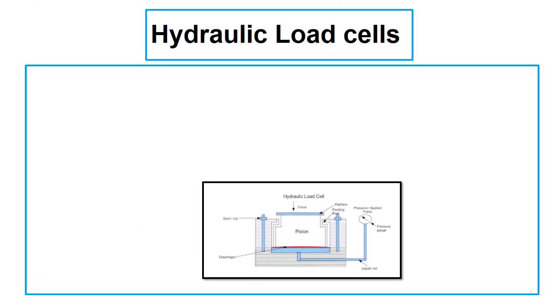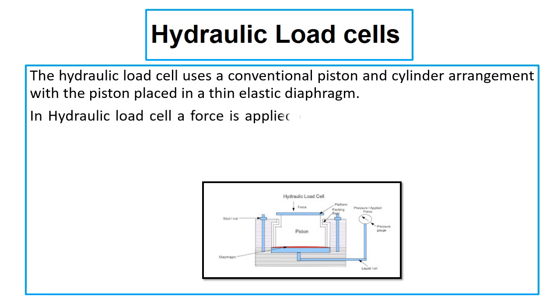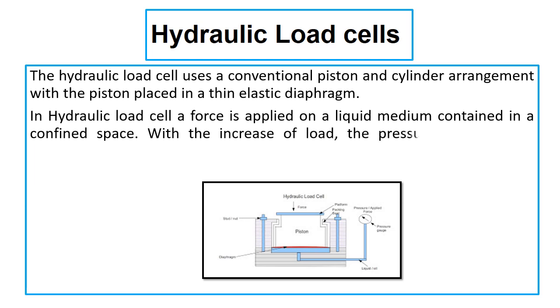Let us discuss the hydraulic load cell. The hydraulic load cell uses a conventional piston and cylinder arrangement with the piston placed in a thin elastic diaphragm. In a hydraulic load cell, force is applied on a liquid medium contained in a confined space. With the increase of load, the pressure of the liquid increases. This increase in pressure of the liquid medium is proportional to the applied force.